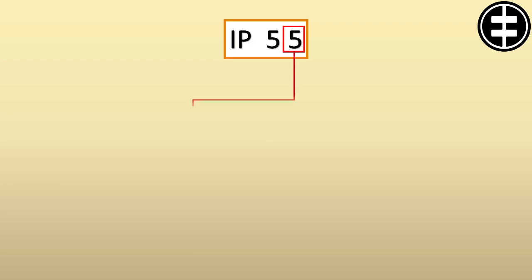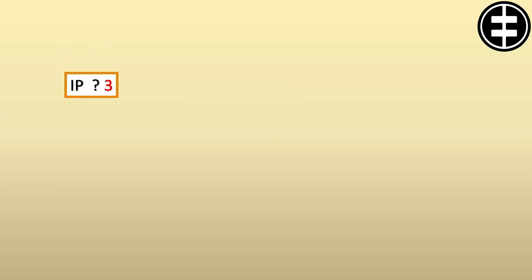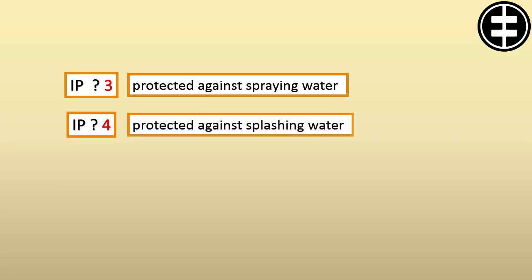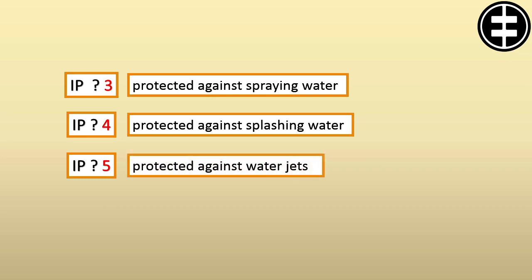The right-hand side digit presents the degree of protection provided by the enclosure with respect to harmful effects due to ingress of water. If this digit is 4, the motor is protected against splashing water.